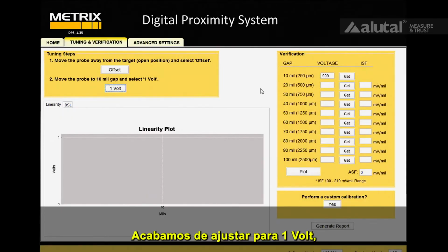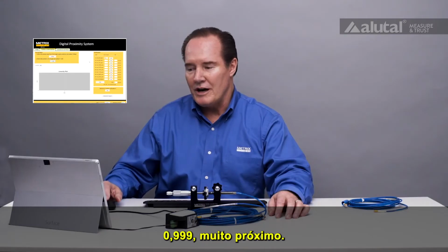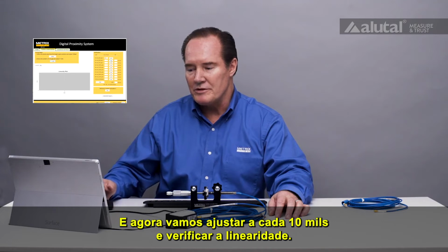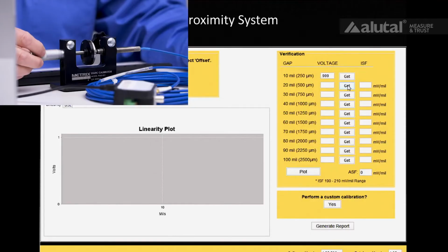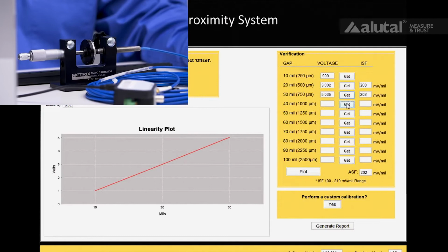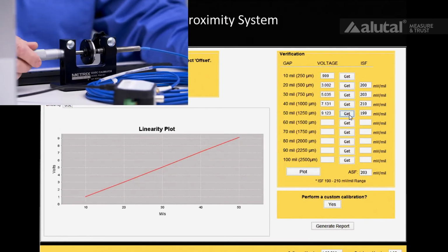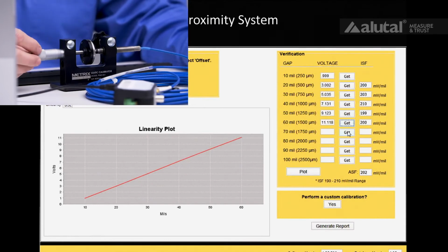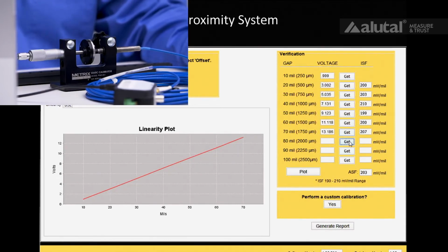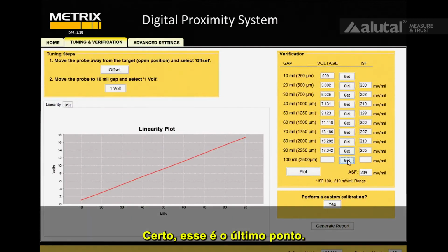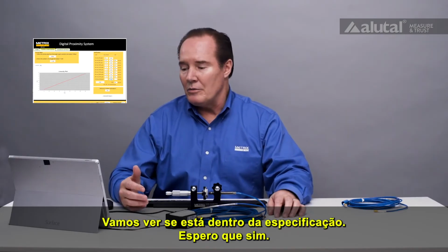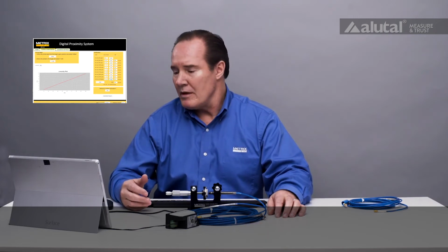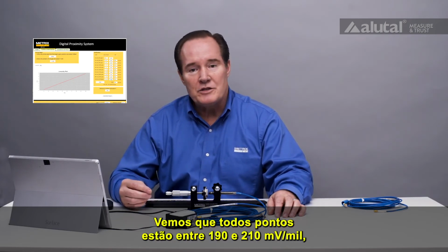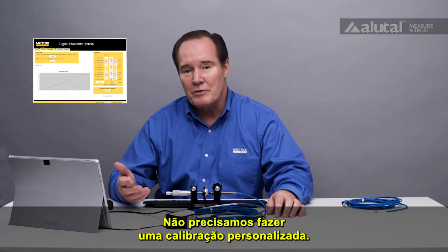Okay, we've just adjusted for 1 volt, and now you can see it's very close to 1 volt, 0.999, which is very close. And what we'll do is we'll adjust every 10 mils and check for linearity. All right, this is our last point, and we'll see if it's in specification. Hopefully it will be. And we see that all the points are between 190 and 210 millivolts per mil, so they're within spec, so we don't have to run a custom calibration.